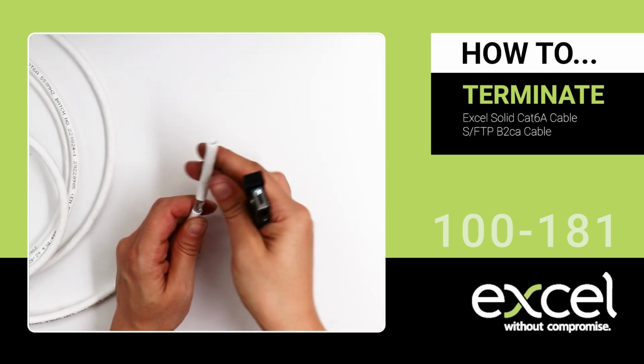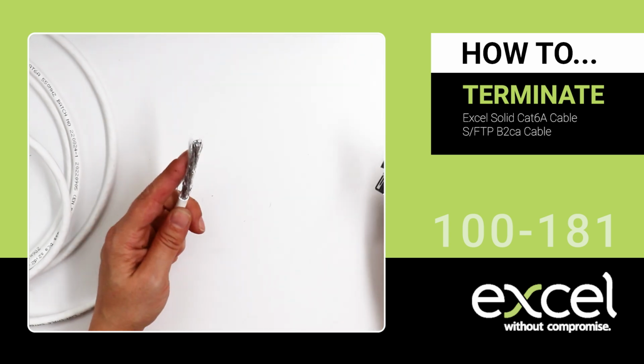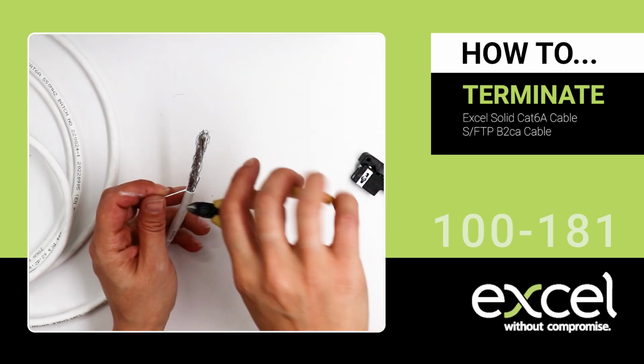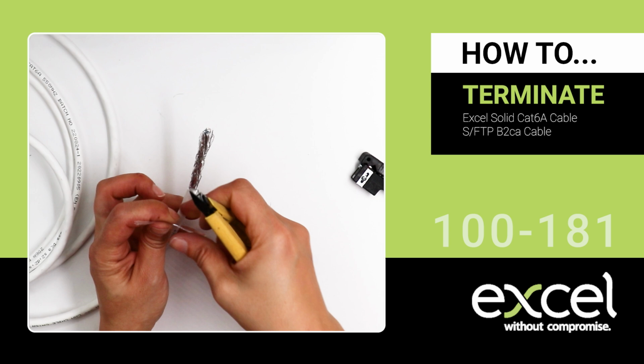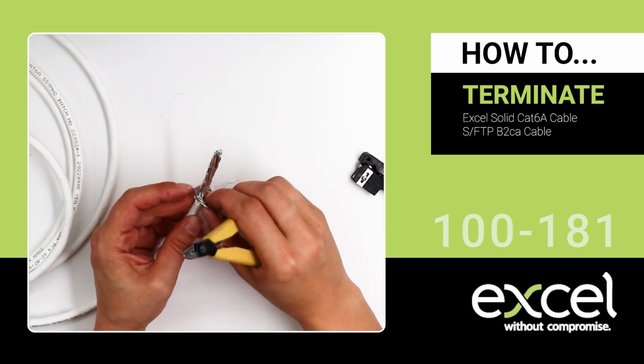Score the sheath, bend the cable to break it, and remove the jacket. Use the multi-purpose side cutters to remove the excess ripcord, then slide the braid down the foil and trim the strands.